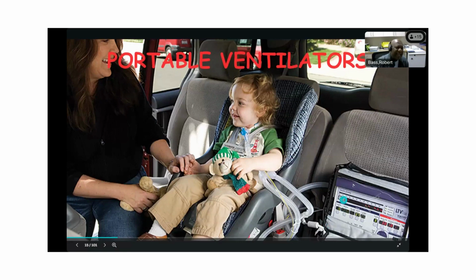The biggest thing that you have to worry about when it comes to these ventilators are the different alarms that go off. You have like a low pressure alarm, a low power alarm, and then a high pressure alarm. And you're going to have on that digital display, you will actually hear the alarm, and it'll identify whether it's low pressure, low power, or if it's high pressure.